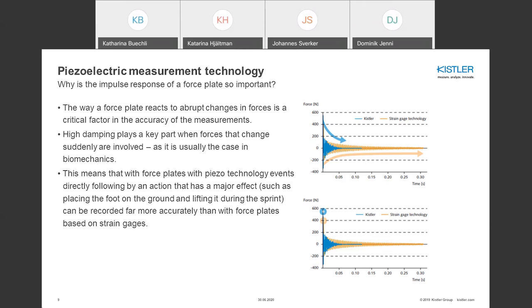The impulse response is critical when there are abrupt changes in force. A high damping factor plays a key part in recording events directly followed by another action. For example, during sprinting when the foot is placed and then lifted, this can be measured far more accurately with force plates based on piezoelectric technology. When an event within the first 0.05 seconds occurs again, a lower ringing response reduces the error.